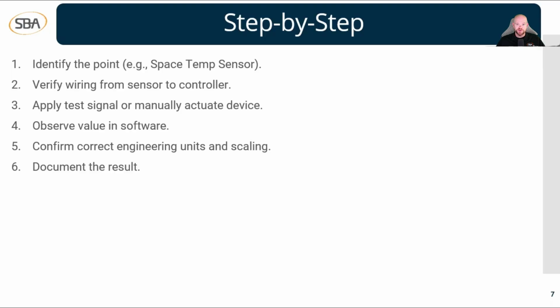Step 5 here is to confirm the correct engineering units and scaling. So this is just verifying your software configuration for this. So make sure that, if this is a space temperature sensor for us here in America, we're going to set that to degrees Fahrenheit, right? So we need to make sure that our software configuration reflects that as well.